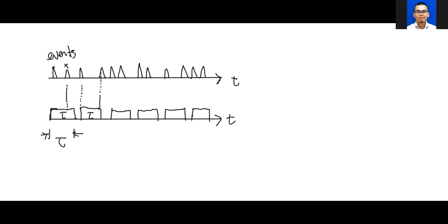So in this consideration again, we have 12, for instance, the true number of events occurs. The system only produces one, two, three, four, five, six, only six counts. And this is the non-paralyzable model of the detector dead time.